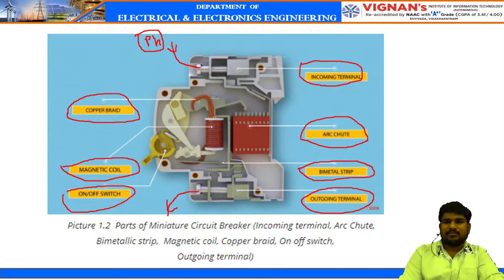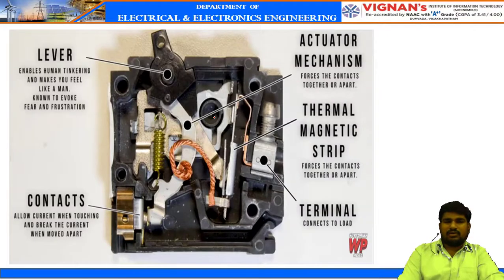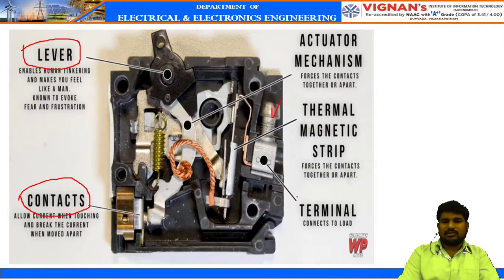This is the practical MCB. We can observe the on-off lever, that is, the on-off mechanism, and we have the contacts, that means the incoming terminal and outgoing terminal. This is the outgoing terminal and this is the incoming terminal. And we can see here the thermal magnetic strip, which is a bimetallic strip.